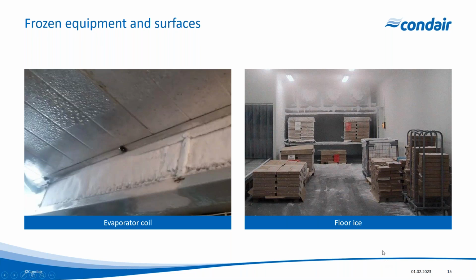We've got cardboard patching that's got ice forming on it, and that's starting to deteriorate and lose its integrity. We've got fog forming at the top of the cold store, so we've got a visibility issue potentially. And we've got ice on the floor, so we've got slip hazards for operatives. And we've got the evaporators starting to ice up as well. So we're going to lose efficiency, and we're going to have to turn those evaporators off at some stage in order to run a defrost cycle.